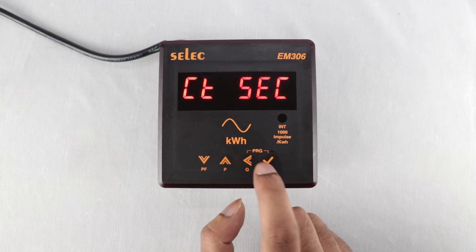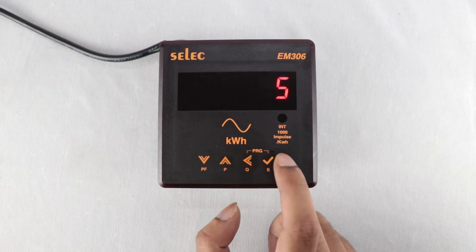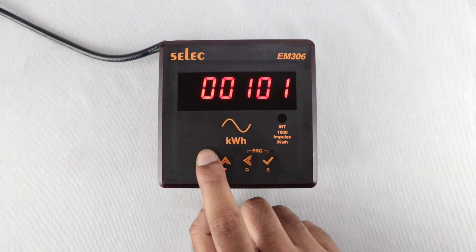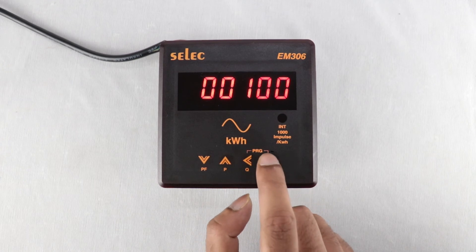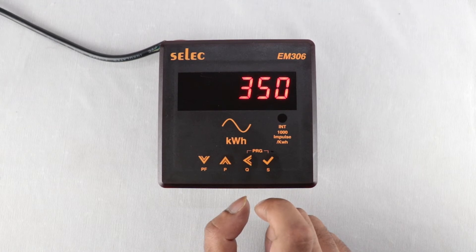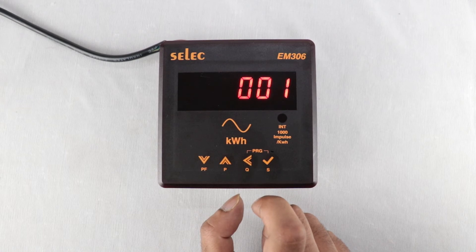For CT secondary and CT primary settings, set any value between 1 ampere to 10,000 ampere — I am setting 100 ampere. For PT secondary and PT primary, set any value between 100V to 500kV. For Slave ID, set any value between 1 to 255.